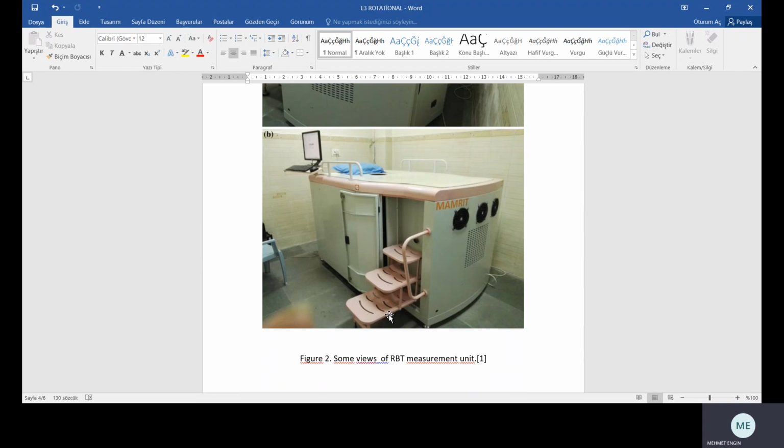The acquisition of temperature information is repeated after lowering the ambient temperature to understand the tissue response to external stimuli. All the images are stored along with the patient information, the camera position, ambient temperature, and time of execution. The sets of thermograms obtained before and after lowering of ambient temperature are called pre-cool and post-cool series, respectively. The same procedure is repeated for the other breast.